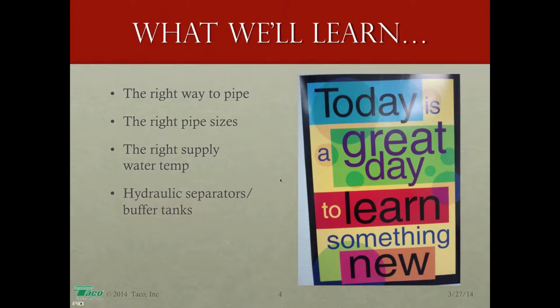So let's get started on the manufacturer's preferred method of piping up a modulating condensing boiler. Every boiler manufacturer's literature that I've looked at over the past couple months to prepare for this all show what essentially is the same piping arrangement. The drawings in their manuals may look unique or a little different, at different angles and different isometrics or whatever, but when you peel all that away, the actual piping strategy for all of them is basically the same.